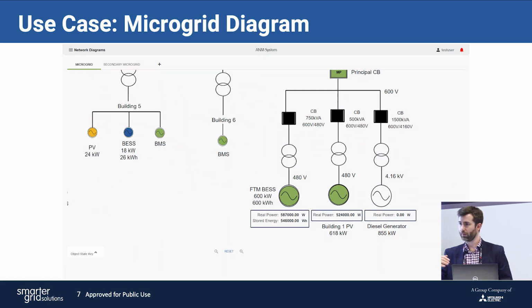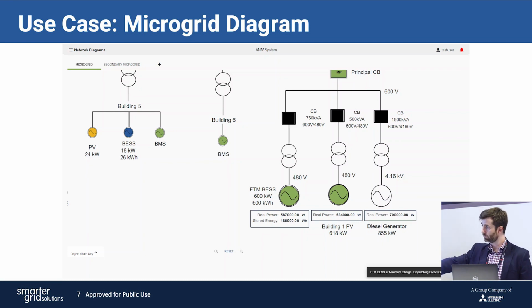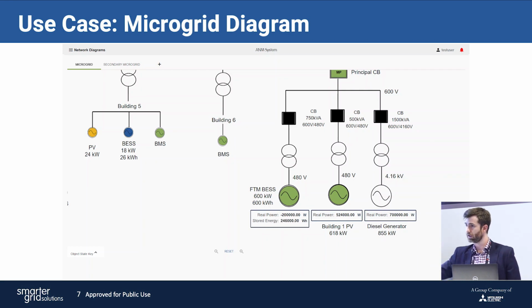What's going to happen here is the battery, the big one on the left, that's our front-of-meter BESS, our grid forming asset. It's currently draining very quickly because this system could be running at 500 kilowatts, and it's only a 600 kilowatt hour battery, so it could drain fast. What's happened just now is it's hit its minimum charge, and we have to transition to diesel power. The grid forming component shifts from the battery to the diesel generator to maintain the live microgrid, and that diesel will allow us to recharge the battery and make the most use of it. Even though we intend for the battery and green renewable energy, the solar, to be the driving power behind this microgrid, we might have to rely on diesel in backup situations - say there's just not the solar, we forecasted solar but the clouds come in. We might have to transition to diesel, and that's what's showing up here: we kick on the diesel to maintain grid stability.